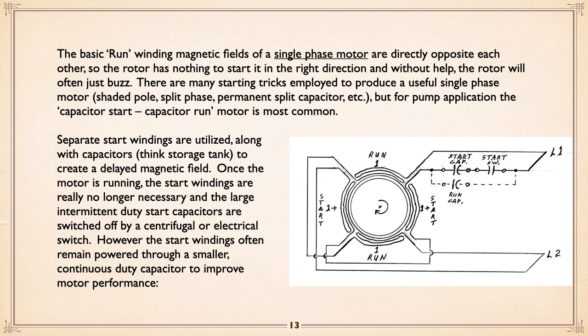And we do that by powering those two start windings, as they're called, on the side, with a very large capacitor, a start capacitor. Because it is so large, we actually turn it off with a start switch. As the power drops off and everything else, the start switch will disconnect that start capacitor. They're designed for fairly short life. You leave them on, they will burn themselves out. But when it flips off, very often, not always, like a typical table saw motor, it's only a start capacitor, and the start switch is centrifugal. But in this case, very often they'll put in a run capacitor, which is a continuous use capacitor, and it really is done to improve the performance of the motor. So the start windings still do something after the motor has come up to speed.